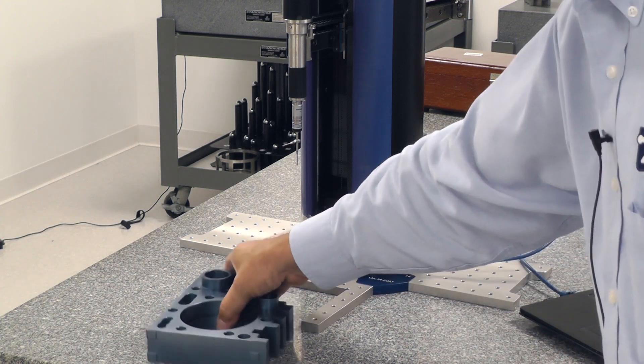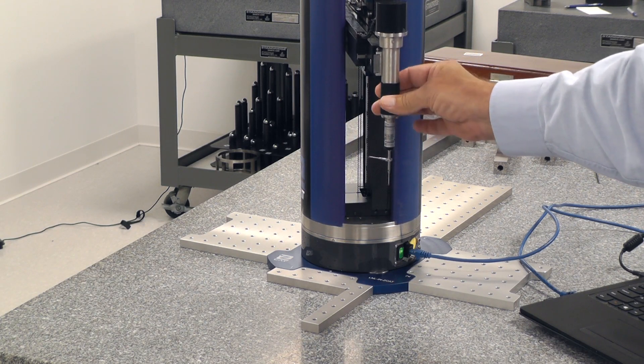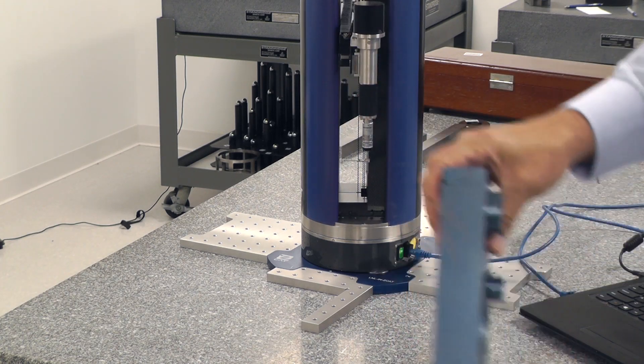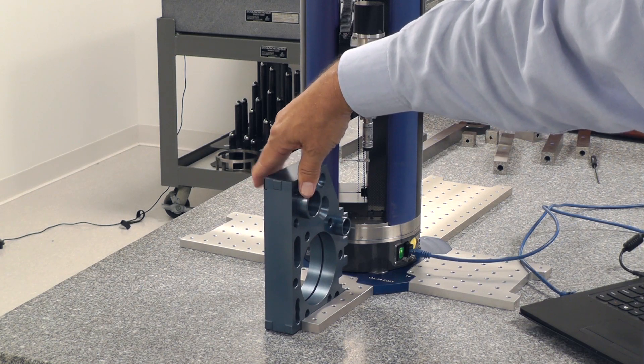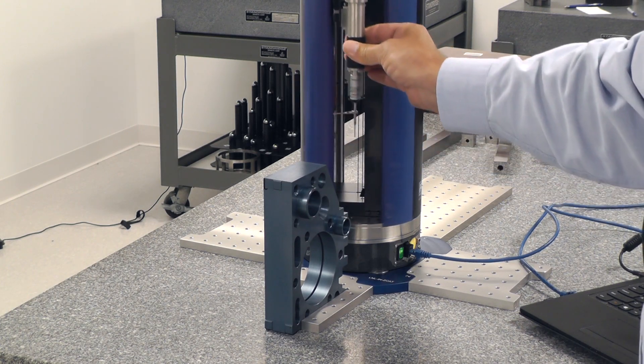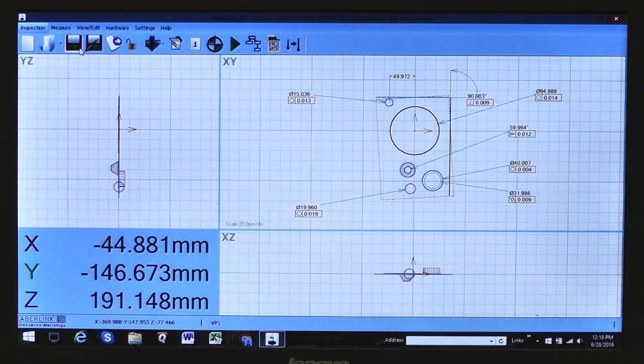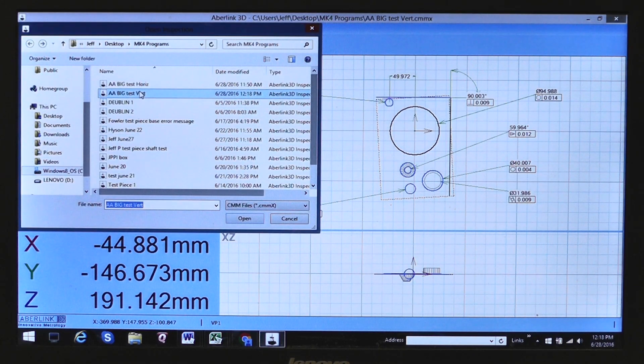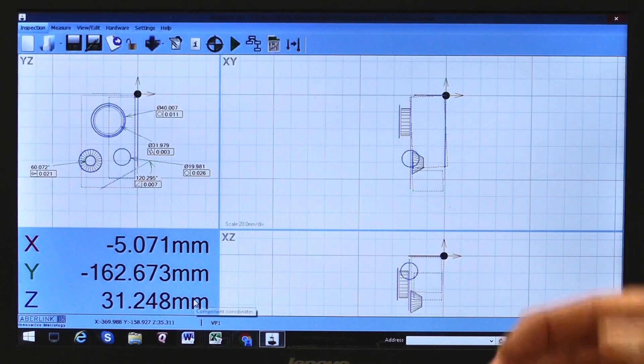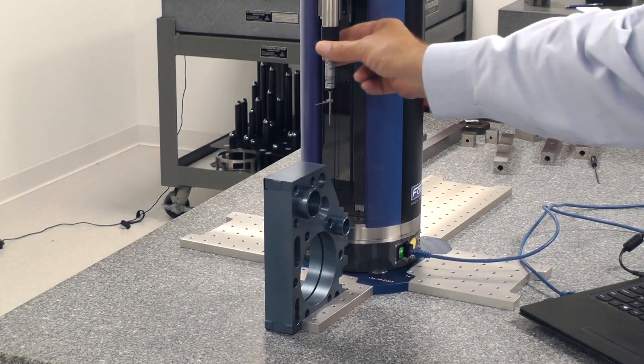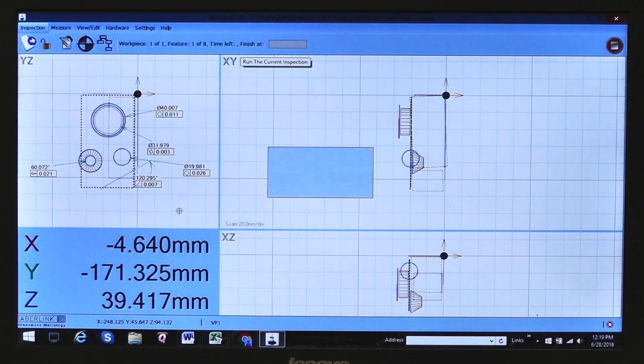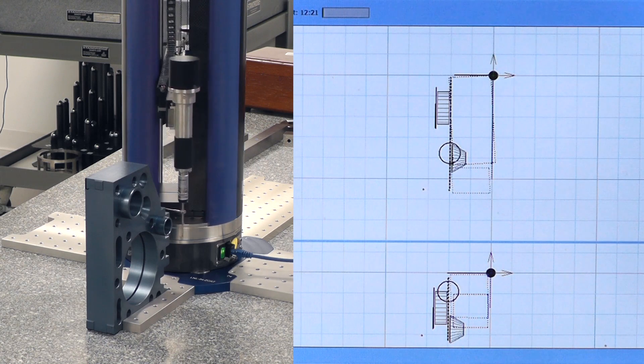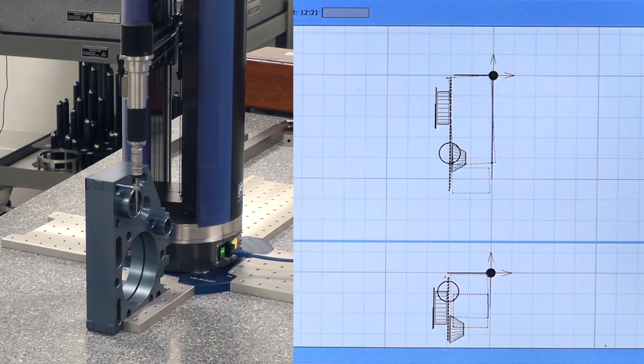Or let's say we wanted to start using the horizontal probe. And you know from the ZCAT, it has both a vertical and a horizontal probe. This probe will rotate 360 degrees. So if I can touch it, I can measure it. So let's say I wanted to measure the same part, but I wanted to do it in a horizontal fashion. So I could come in here and measure features using the horizontal probe. I just happened to have written it. I can save this data on this program. I can go back until I want to open another program. In this case, I'll do the horizontal probe. I'll double click on it. And now it brings up a different program on the same part to measure some dimensions using the horizontal probe. So I'll just get the ZCAT in position, and all I'll do as an operator is hit the play button. You'll see that it switched to the horizontal probe on the screen. It also switched to horizontal probe one. And now it's going to measure a lot of the same features using the horizontal probe.